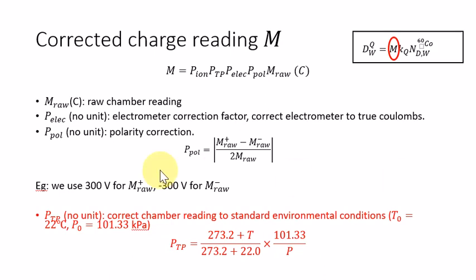PTP is calculated by this equation. Basically, as we just mentioned, it corrects the chamber raw reading on any temperature and pressure condition of the day of the TG51 measurement back to standard environmental condition, which is temperature equals 22 Celsius degrees and pressure equals 101.3 kPa. The correction factor is calculated by this equation.